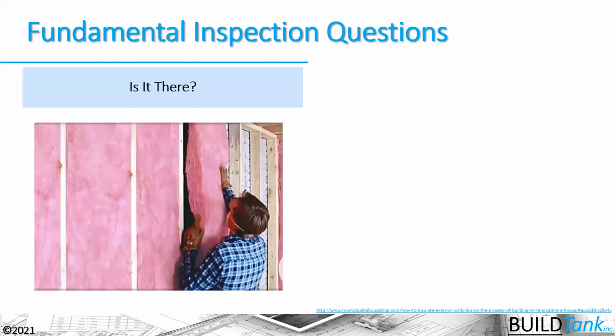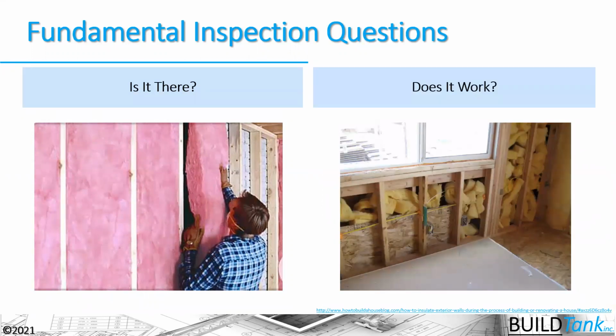So we need, again, to not only on the thermal envelope side, ensure that the specifications are there. In this case, this fiberglass batt is being installed. I can't, however, just walk in and say, yes, I see pink in the walls and walk out. I have to actually look at how it's been installed. And has it been installed to actually achieve the R value that has been specified? Or have the building cavities been used as a trash can instead? These are the things that we see on site. But on the HVAC side of the equation, that manipulation we can guard against as well.